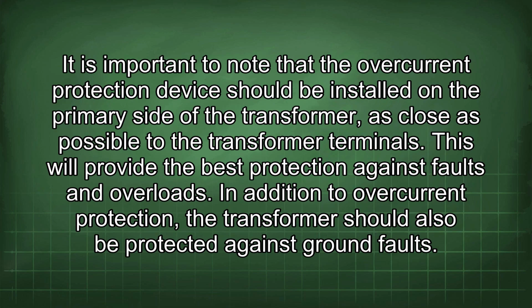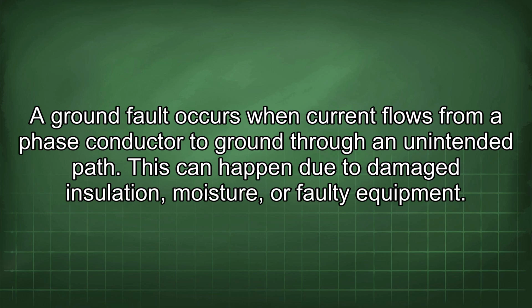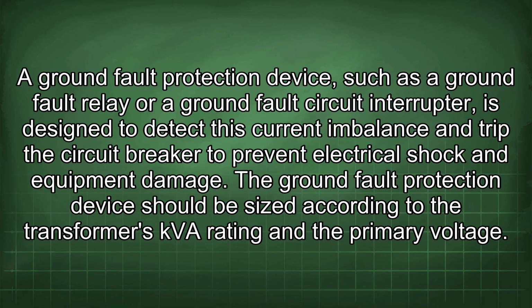It is important to note that the overcurrent protection device should be installed on the primary side of the transformer, as close as possible to the transformer terminals. This will provide the best protection against faults and overloads. In addition to overcurrent protection, the transformer should also be protected against ground faults. A ground fault occurs when current flows from a phase conductor to ground through an unintended path. This can happen due to damaged insulation, moisture, or faulty equipment. A ground fault protection device, such as a ground fault relay or a ground fault circuit interrupter, is designed to detect this current imbalance and trip the circuit breaker to prevent electrical shock and equipment damage.